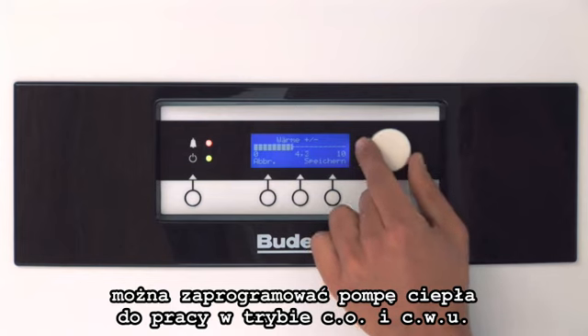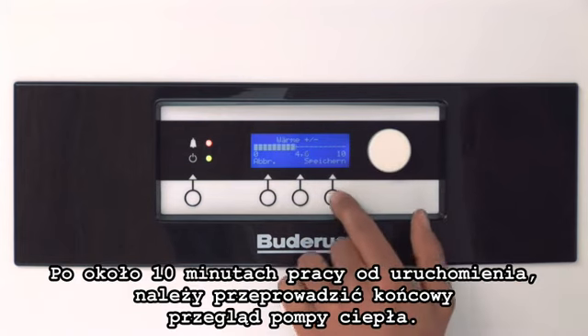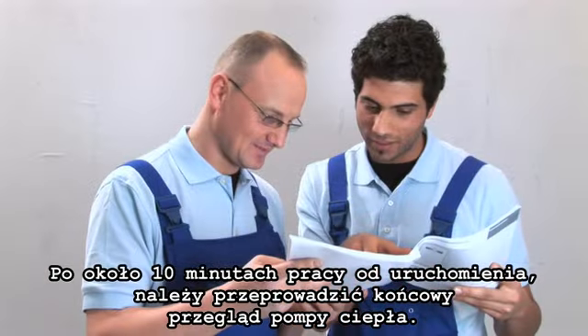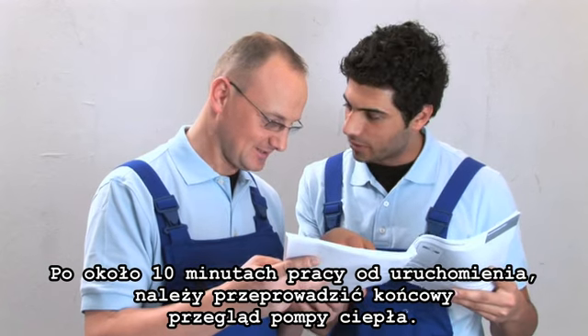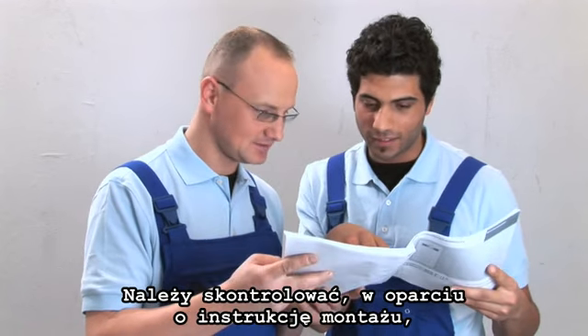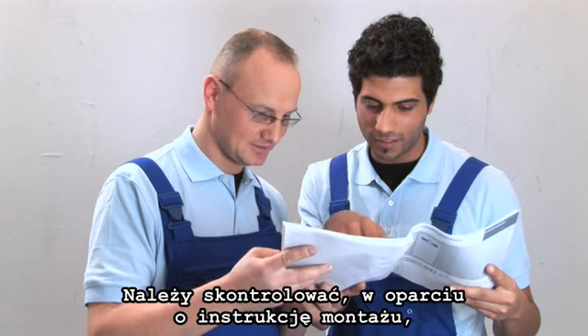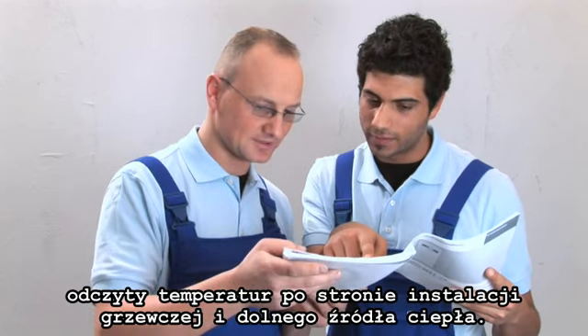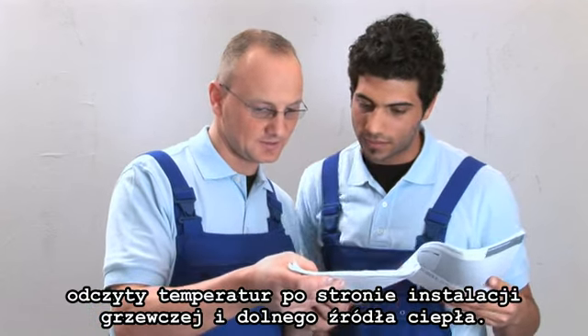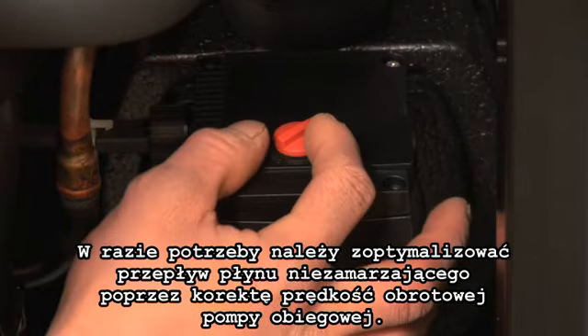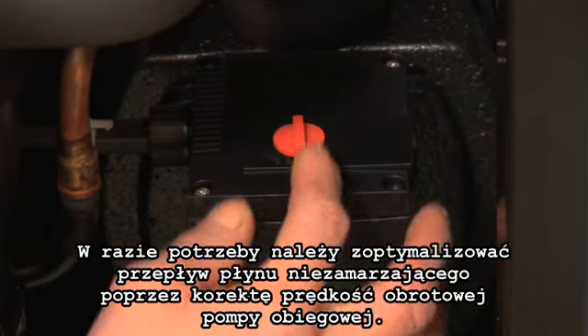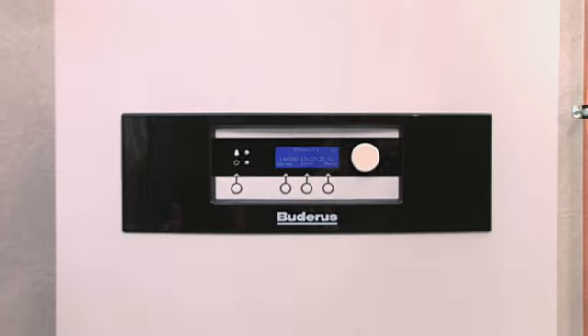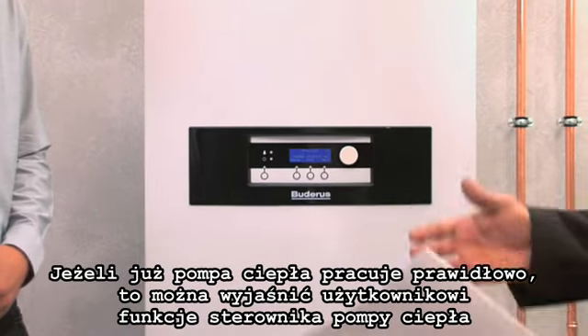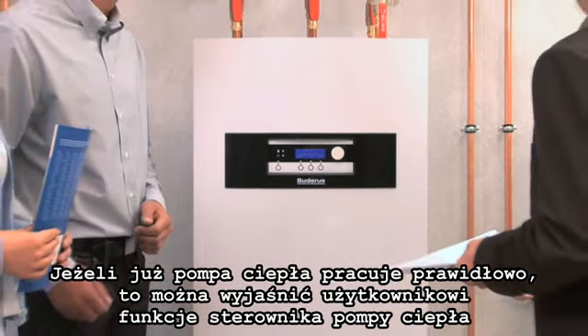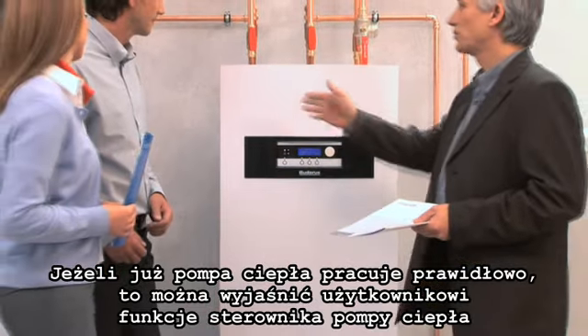About 10 minutes after the commissioning, the final inspection of the heat pump is carried out. Now check, using the installation instructions, the spreads on the heating side and on the brine side. If required, optimize the values by adjusting the pump revolutions. If everything is all right and the system is running stable, you can explain the functions of the heat pump to the owners.